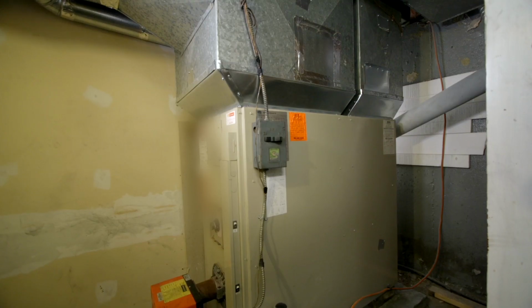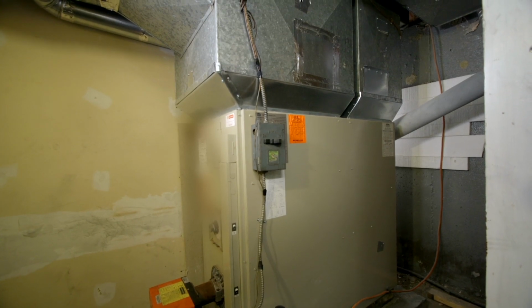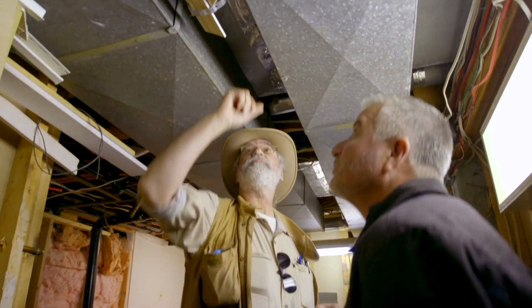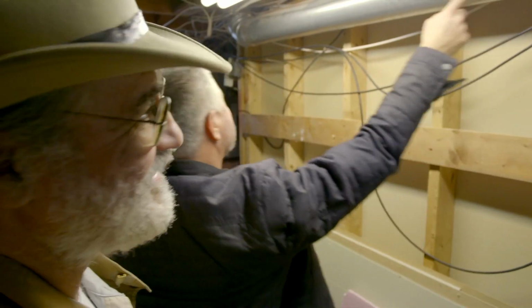These old oil furnaces had very high temperature rise. It's not warm, it's hot. With the heat pump, the air coming out of it is warm, it's not hot. So you need more airflow to get the same heat. The question is, can the existing ductwork carry the higher level of airflow?